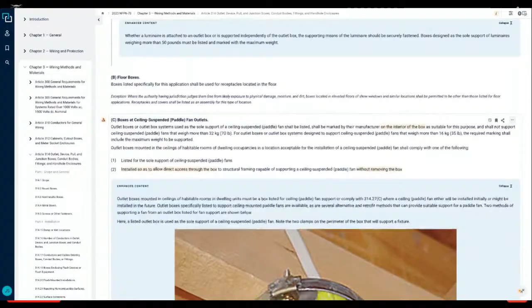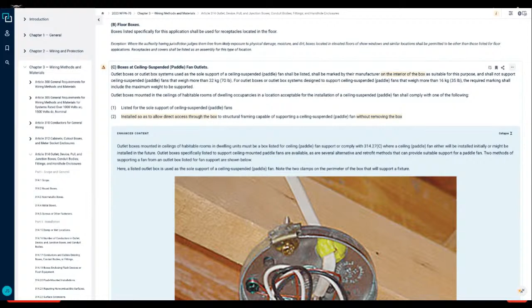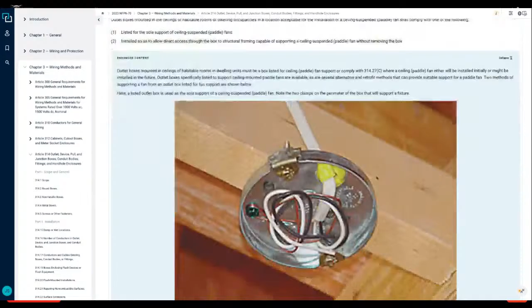Now listen to what this says. I'm looking at C. It says outlet boxes, or outlet box systems. So when you buy one of those at the store where you can twist it and it goes across those studs and anchors in, that's an outlet box system. They're telling you the box itself is the outlet for that luminaire or paddle fan. Now, if I'm reading this and following along, it's telling me to do exactly this.